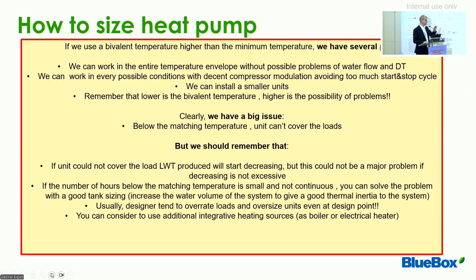So, just doing a quick summary of this. If we select a higher bivalent temperature, we have seen that there will be some hours during the year that we cannot meet the heat load, okay? But then we could still cover the load, reducing the leaving water temperature produced. Or if it's a small number of hours, we can play with a good sizing of the water tanks, the water volumes of the circuit.